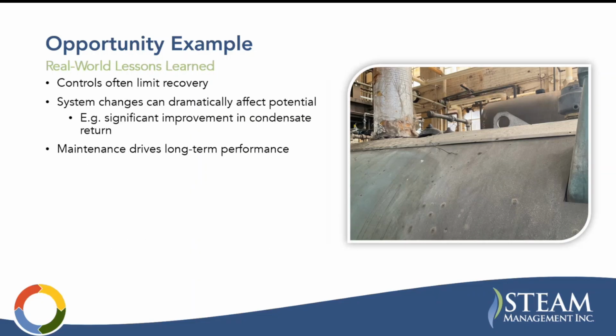Some lessons learned: controls often limit recovery. System changes can dramatically affect potential. So a significant improvement in condensate return could potentially significantly reduce your blowdown and thus your energy source. And then also maintenance drives long-term performance. So these things do have to be maintained. Sometimes it can be years between cleanings. I've seen recommendations that you clean after the first year, maybe clean after the second year. If it's not that dirty, maybe you can extend that out, but you do have to plan for some maintenance. But it's a significant energy source.